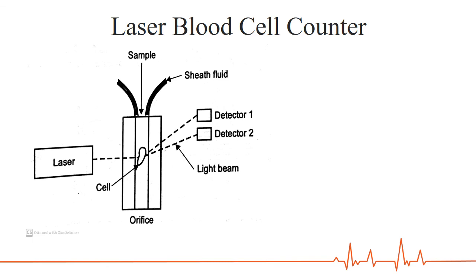How to separate this? To separate white blood cells from the RBC, we need to destroy the red blood cells within a lysing agent. Hence, this frees the hemoglobin from the blood and the concentration of the hemoglobin can also be measured. After the separation of the hemoglobin, once again the measurements are made. By this way, the concentration of white blood cells too can be measured.